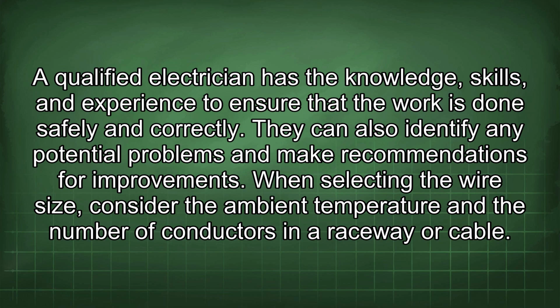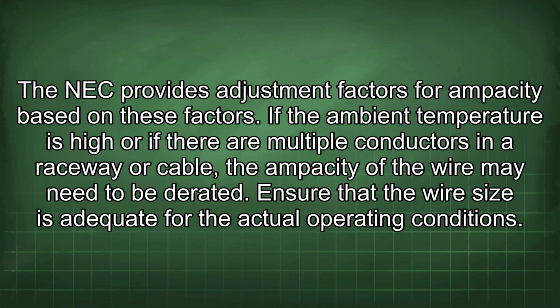When selecting the wire size, consider the ambient temperature and the number of conductors in a raceway or cable. The NEC provides adjustment factors for ampacity based on these factors. If the ambient temperature is high, or if there are multiple conductors in a raceway or cable, the ampacity of the wire may need to be derated. Ensure that the wire size is adequate for the actual operating conditions.